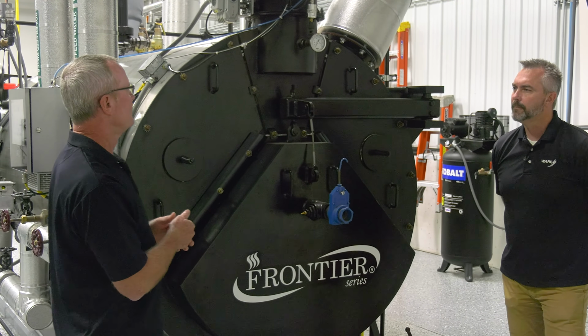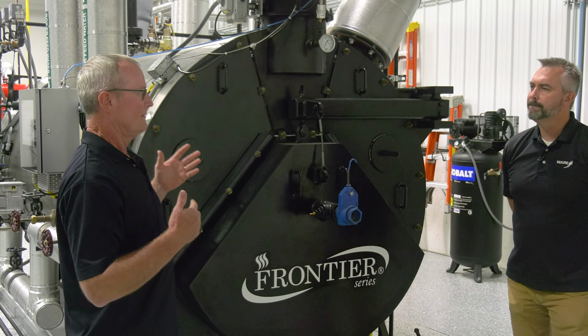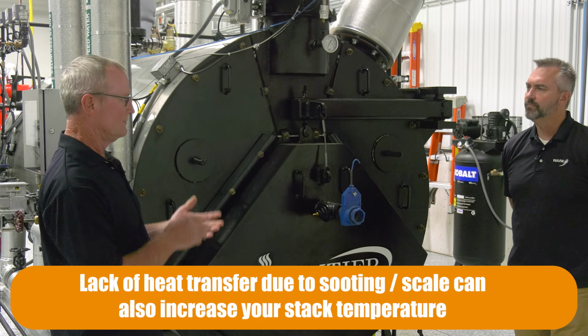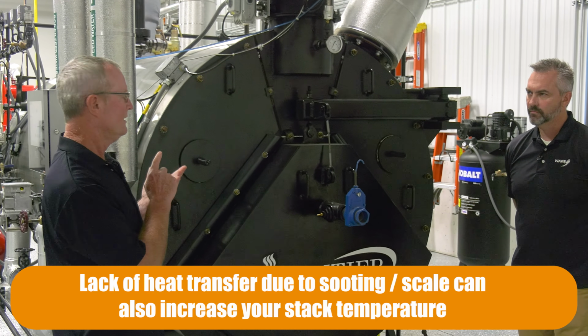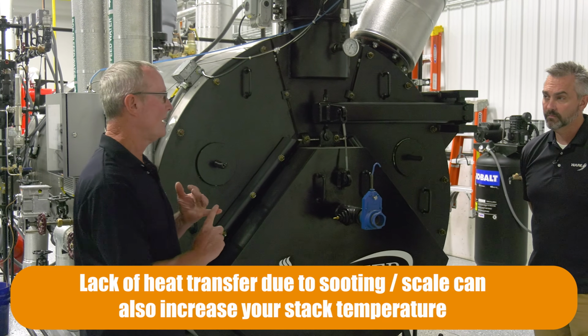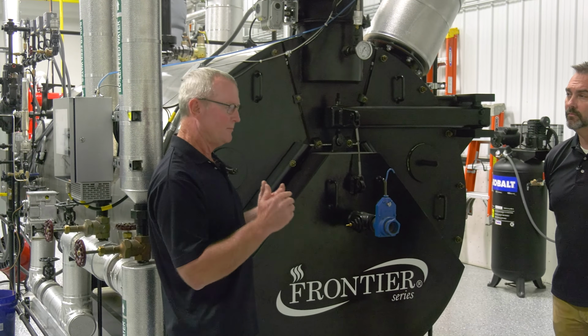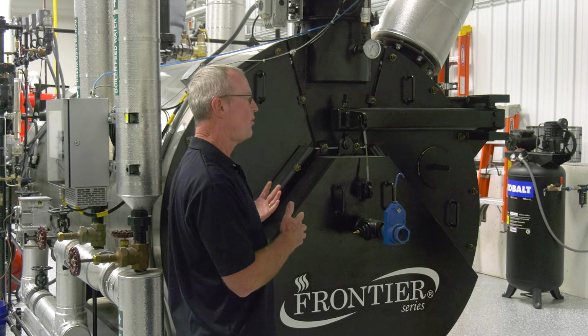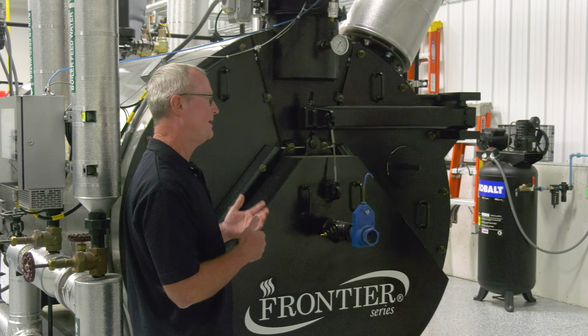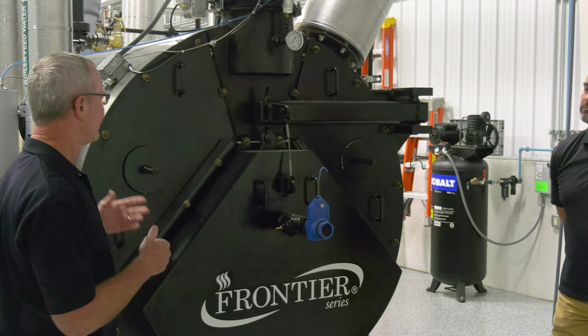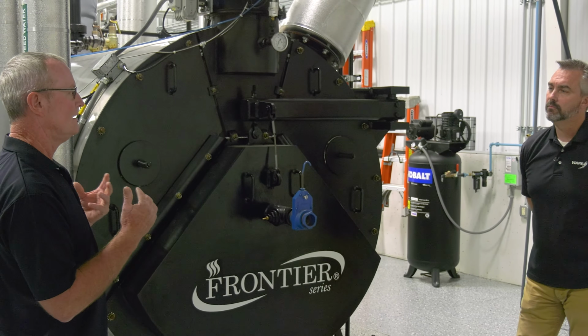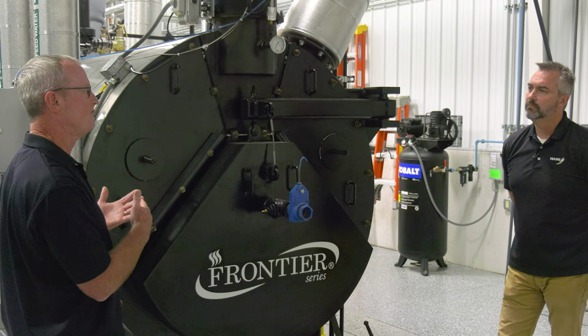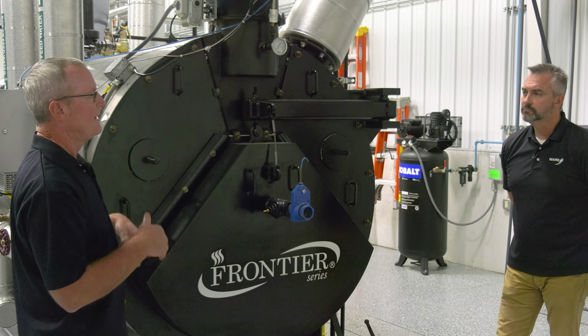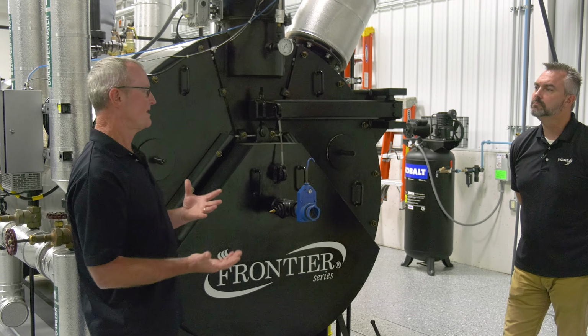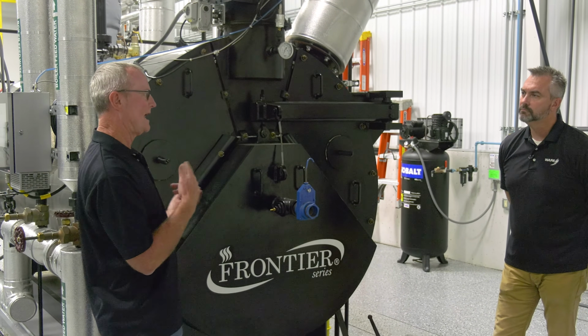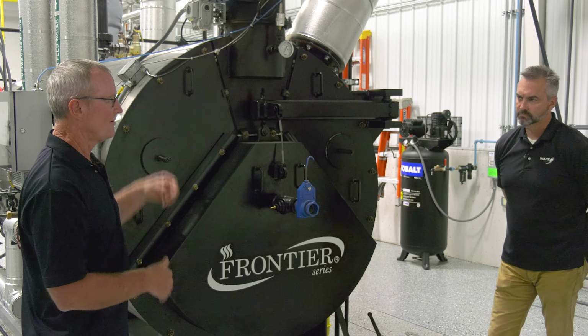The other thing that will do that is lack of heat transfer. 2 things cause that. One, if you soot the boiler up, you soot those tubes up, because typically that's oil firing. If you soot the boiler up on gas firing, you've really got a bad combustion. Right. But it can happen. So that creates insulation on the fire side of the boiler, so you can't get heat transfer. Your stack temperature goes up. Same thing on the water side. If you start to scale it up, it does the same thing. Lack of heat transfer, your stack temperature starts going up.